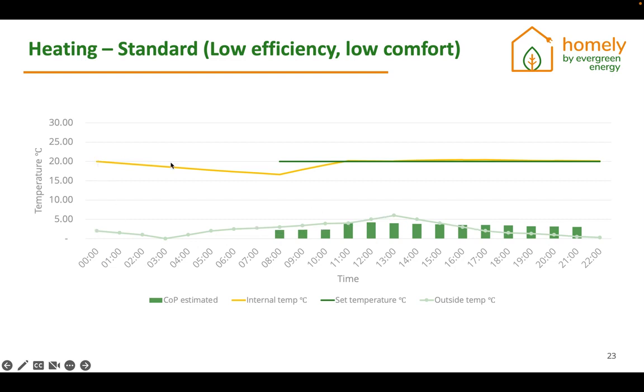What we can see from this graph is that a customer has a set point between 8 o'clock and 10 o'clock in the evening. So the customer has a set point of 20 degrees throughout the whole day. They are in standard mode, which means that the heat pump is not allowed to run outside of these times. And if we start off at 12 o'clock at night at 20 degrees indoors, the house is actually going to be cooling down all the way up to 8 o'clock in the morning, at which point the heat pump will kick in and go full blast to get the internal temperature of the house as quickly as it can to the desired set point of 20 degrees that the customer has selected.